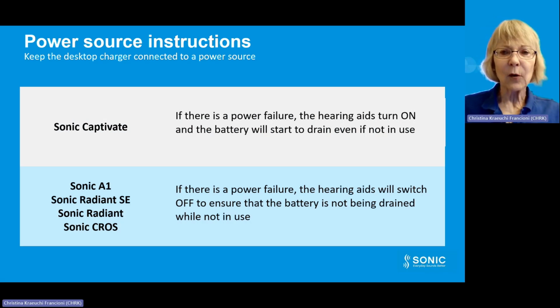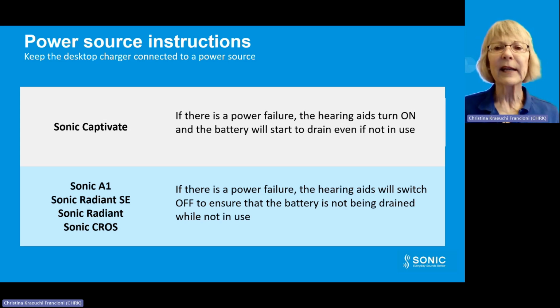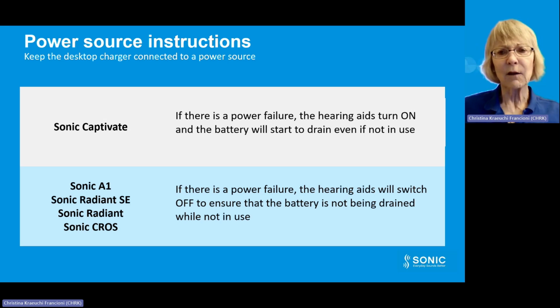It is important to keep the desktop charger connected to a power source while the hearing aids are in the charging ports, regardless of which Sonic hearing aids your client has. If there is a power failure or if your client accidentally disconnects the charger from the power source, the following will happen. For Sonic Captivate, losing power will trigger the hearing aid to turn on and start using the battery, meaning that the hearing aids may be fully drained when your client needs them. For Sonic A1, Sonic Radiant and Radiant SE, and Sonic CROS Transmitter, a charger losing power will trigger the hearing aids to switch off automatically to ensure that the battery is not being drained when not in use.